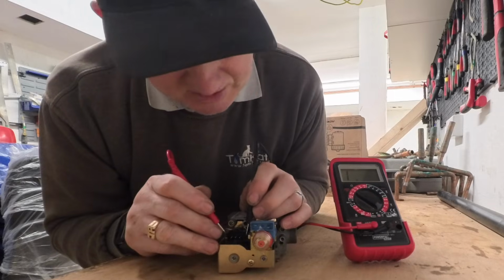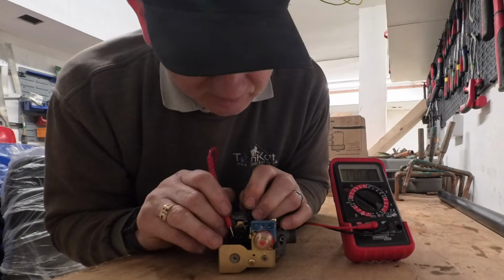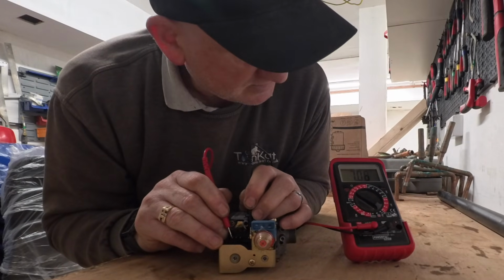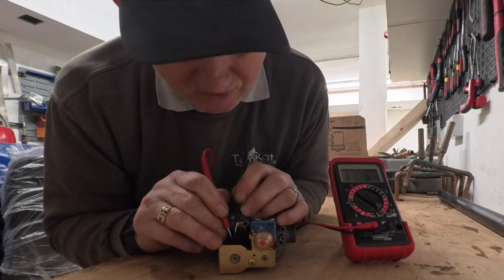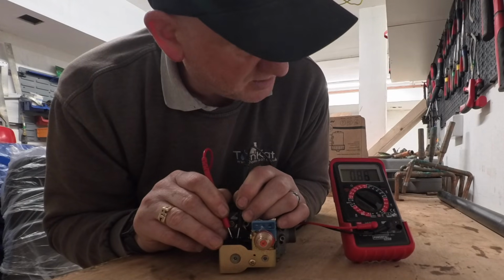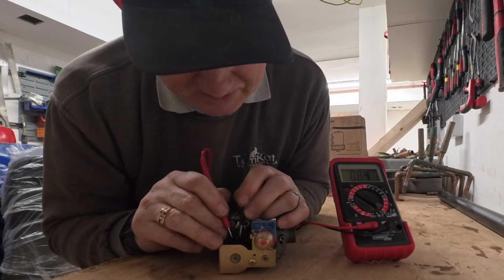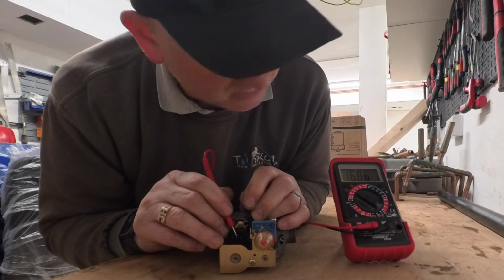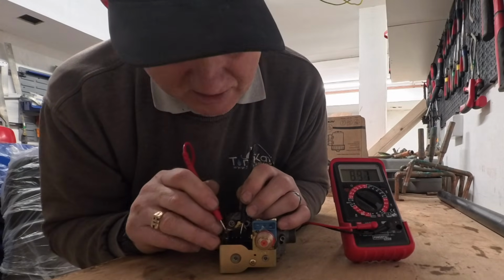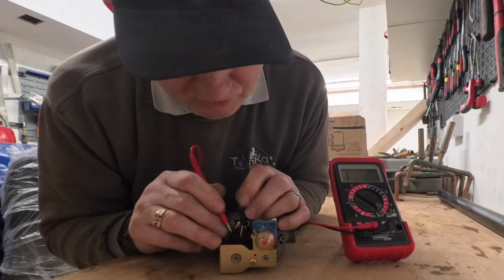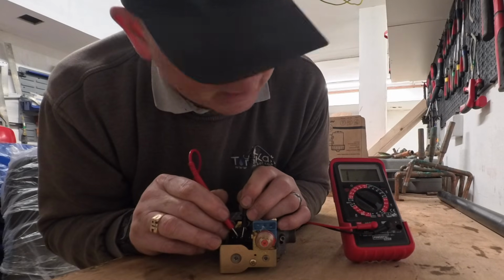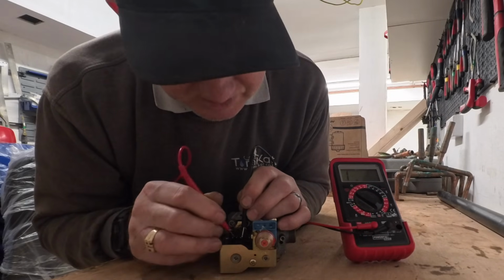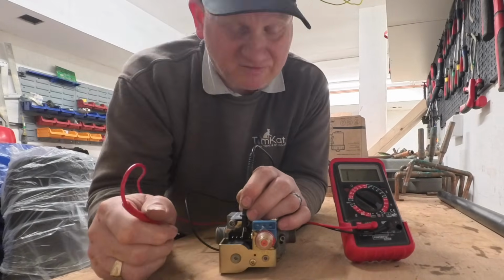So again, if I go on the two outer ones, we've got a reading. If I go between these two, we've got a reading. And if I go between those two, we've got a reading. And if I go back on the earth, we should have no open line, which we don't. So both these gas valves are good.